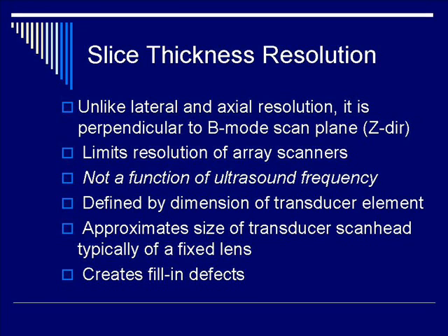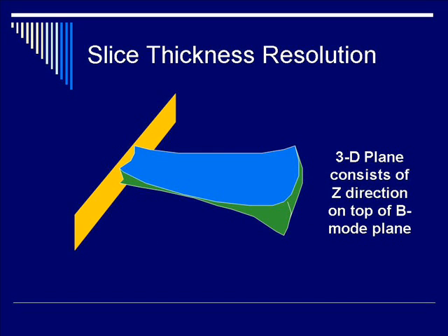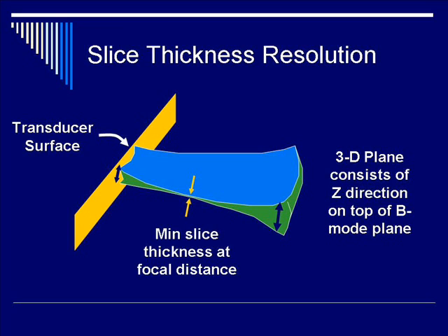Clinically, it creates a fill-in defect if you're measuring away from the focal zone. Here's a cartoon of the spatial variation of the slice-thickness plane. You can see that near the transducer surface, you have a finite thickness of the z-direction. It gets even bigger in the far field away from the focal zone. However, right at the focal length, slice-thickness is minimum.